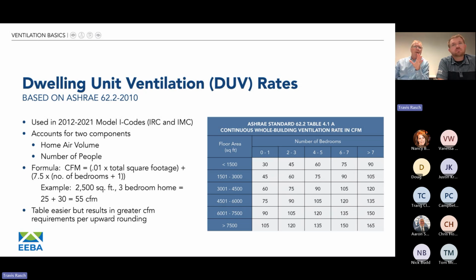So here again, we're going to switch gears and talk about dwelling unit ventilation, whole home continuous ventilation. Ever since the 2012 model codes, this is where the energy code started requiring it. This is based on ASHRAE, the 2010 level. As ASHRAE was determining how much fresh air people need, they came up with the formula: 1% of square footage plus 7.5 CFM per person. To estimate the number of people in a home, they use number of bedrooms plus 1. The proxy being, bedrooms probably each have 1 person, but the master bedroom probably has 2. Your typical 3-bedroom home probably has 4 people, parents and a couple kids.